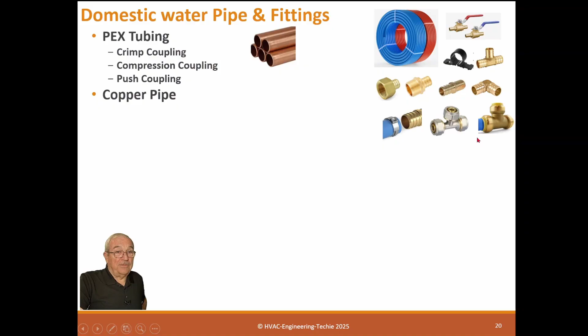Copper pipe, which comes in tubing sizes. It has ball valves. Normally we should use ball valves everywhere. We still have gate valves and globe valves, but the ball valve is so much superior for water service. What happens is the other valves fail due to corrosion or whatever, and the ball valves do not. So the ball valves have stainless steel balls and brass fittings. And then, of course, we have unions, copper unions.